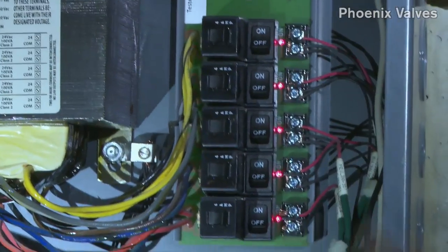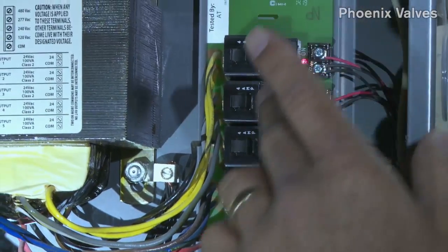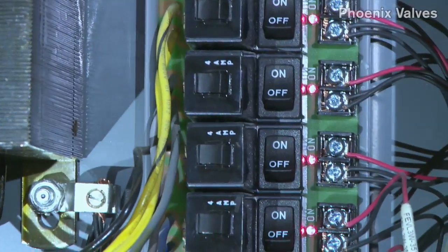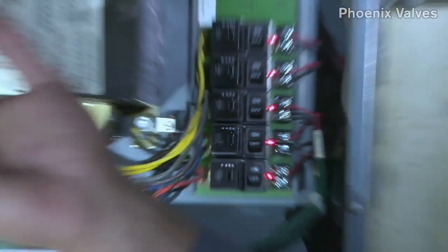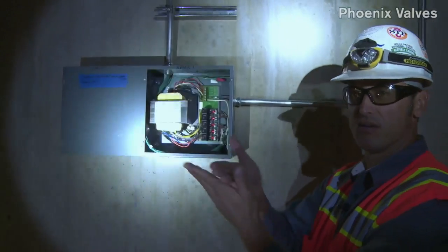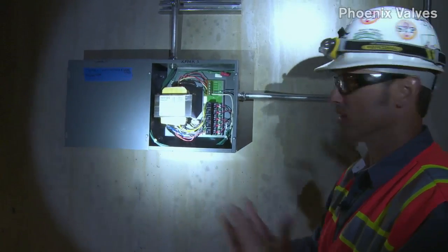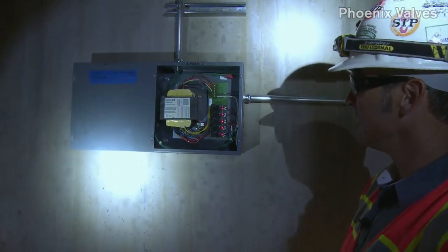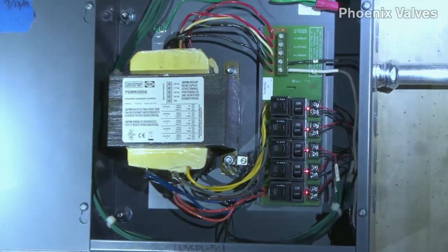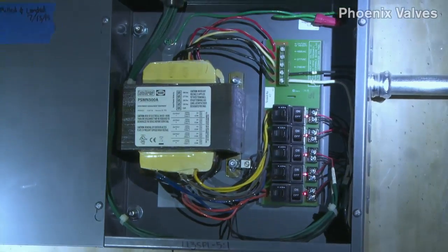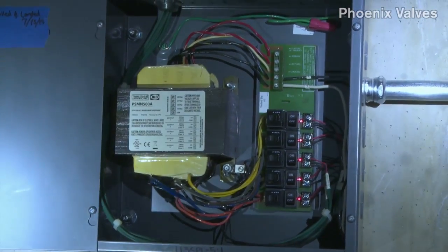All you have to do, if the red light is off, is turn it off first, and then you should be able to just push that and reset it and then turn it back on. If it trips again right away, then you have a problem somewhere in the wire. You just got to go find out. It could be that somebody put the cover on and it sheared the jacketing on the wire to where it creates a ground in it. But that's where I would start if you don't have any lights on your controller when you first go to it.